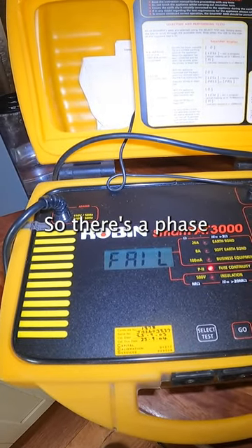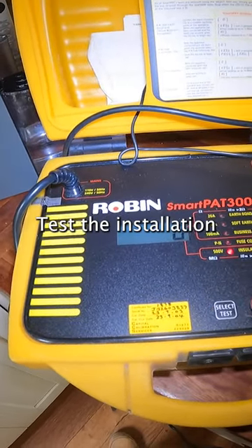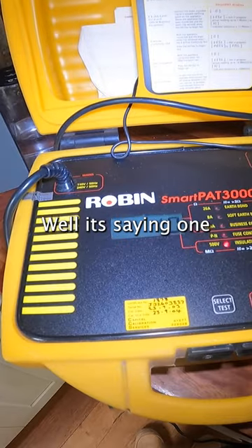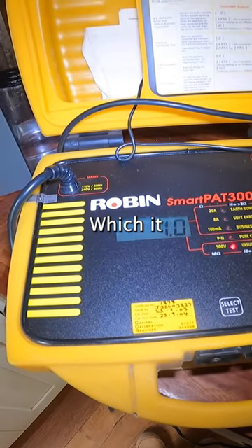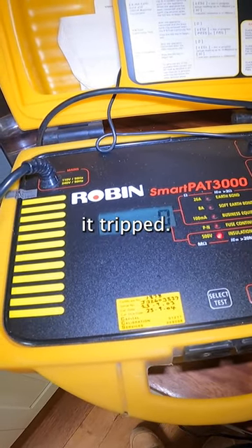Failed — so there's a phase-to-neutral problem. Going down to the next test: the insulation resistance. It's saying 1 MΩ, which should be greater than that. There's a phase-to-neutral fault on it — that's why it tripped.